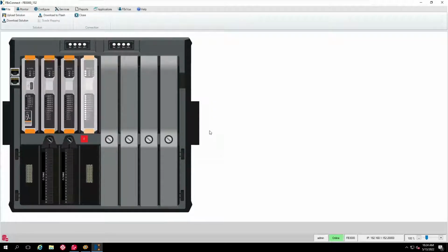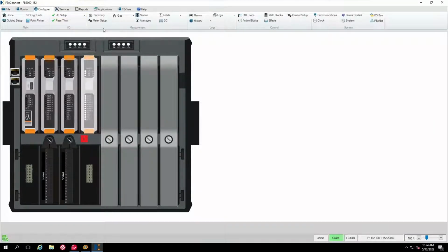If we then look at the flow rate alarm and generate some flow rate alarms, enabling and disabling them and changing the alarm limits, we'll be able to see those alarms and the associated configuration events being logged in the RTU. And then later we can see those within AUTOSOL ACM, and then we can change how those are mapped within AUTOSOL using alarm and event maps. So first we need to connect to the RTU, and then we need to look at the configuration of the station.